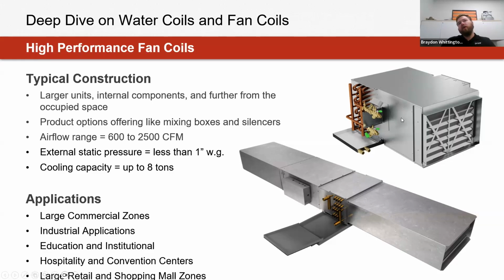Another one too, which is almost the big brother of some of those commodity horizontal units, is what you'll notice here. Instead of adjusting the width, we're adjusting the height. Similar benefit of air pressure drop and adding a higher amount of airflow that can be provided from these units. And these ones are kind of that bridge point once we start to get around that 0.5 to 1 inch of static that this fan's trying to compensate for, where it might make sense, not quite making sense for that first initial cost of a blower coil, but not enough capabilities of a concealed or commodity type for being able to handle those conditions. So yeah, with these ones, larger spaces where we might see these, whether it be educational rooms, a cafeteria, and larger commercial zones, or even within bigger spaces there too.